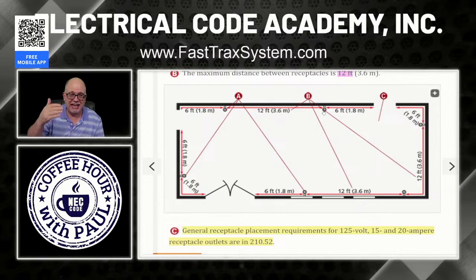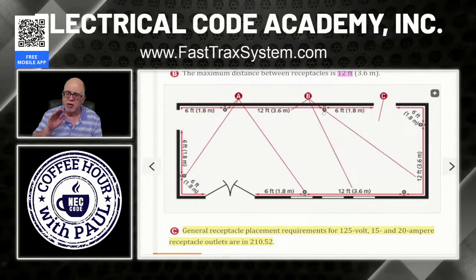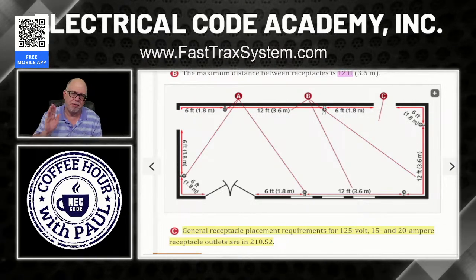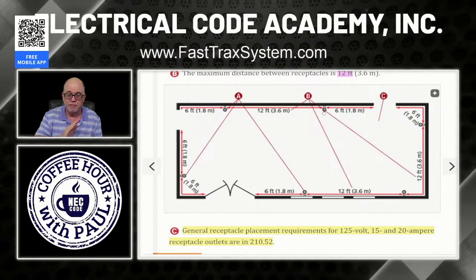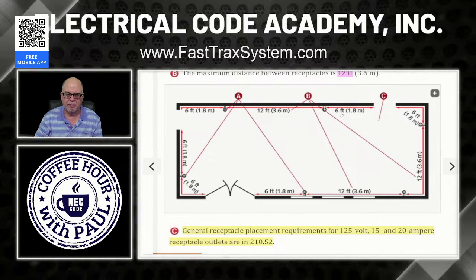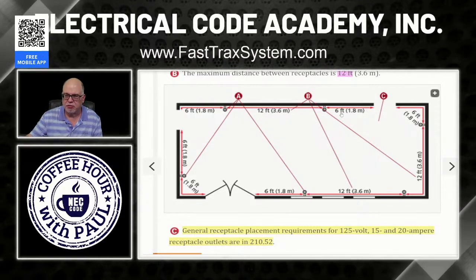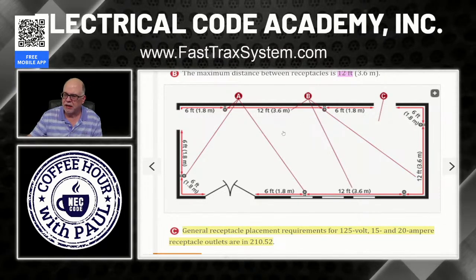That doesn't mean that I can't have a receptacle above 5.5 feet. Sure, I can. But I still have to have a receptacle down below 5.5 feet to meet my placement requirements around the room. Make sense? So again, you'll see a lot of people that'll have the TVs with the receptacles behind it, and they'll be feeding them from a receptacle that's down low that's meeting the spacing requirement, but they needed to just get power up higher so they can supply that flat screen TV. Perfectly okay to do that, but you got to remember the spacing rules, okay?